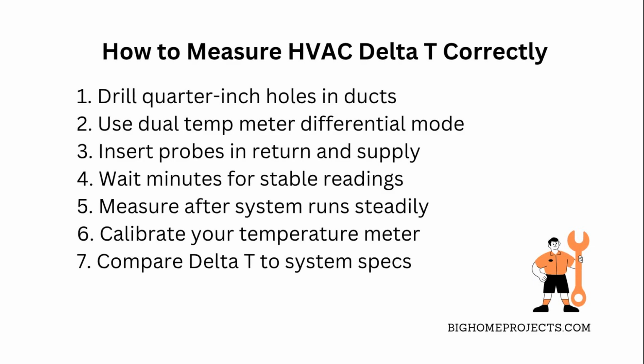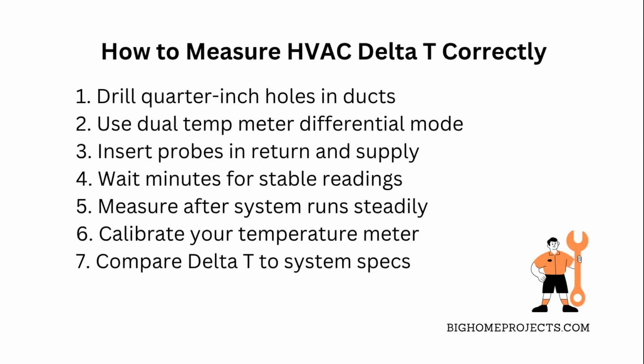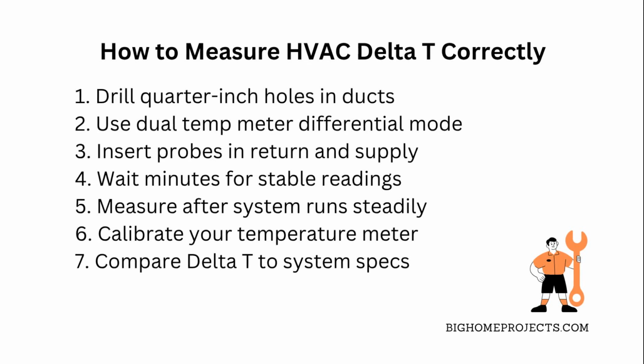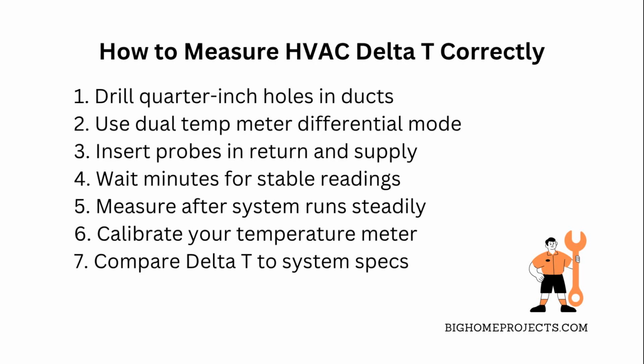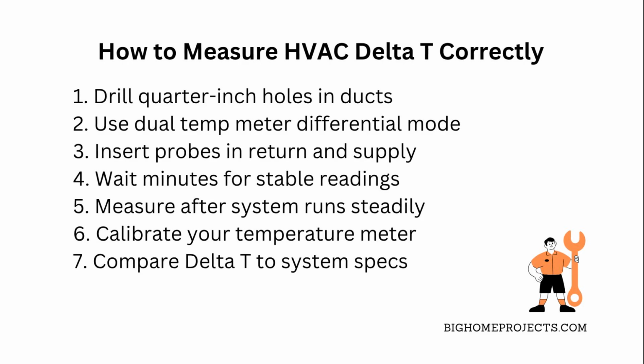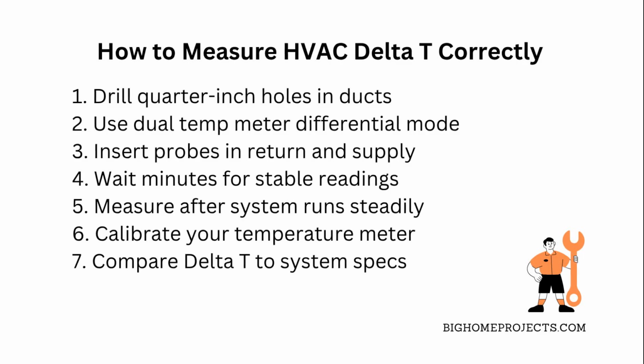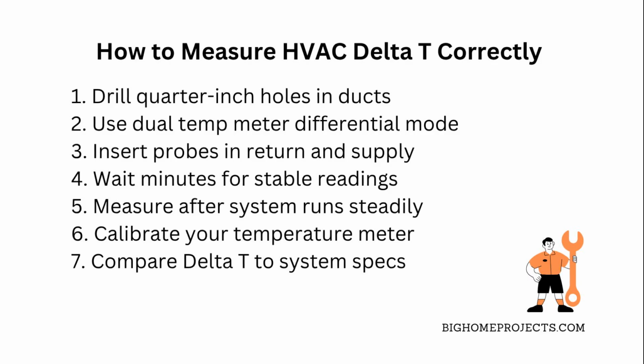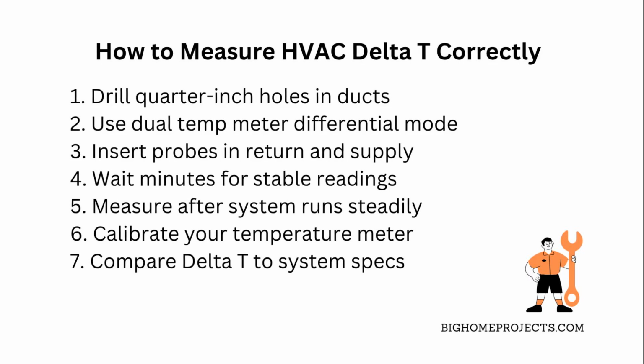Then, grab a dual temperature meter and set it to differential mode so it shows the temperature difference between the two probes directly. Stick one probe in the return duct hole and the other in the supply duct hole. Wait a few minutes for the temps to stabilize, because you want accurate readings that reflect real HVAC performance, not some quick spike or dip. Make sure you're measuring when the system has been running steadily for at least 5 to 10 minutes. Also, double-check your meter's calibration to avoid any funky numbers.